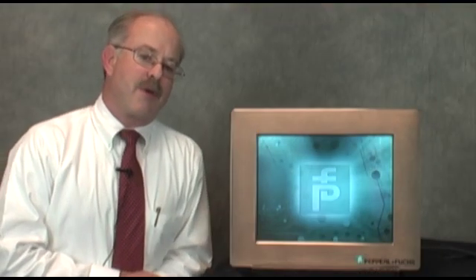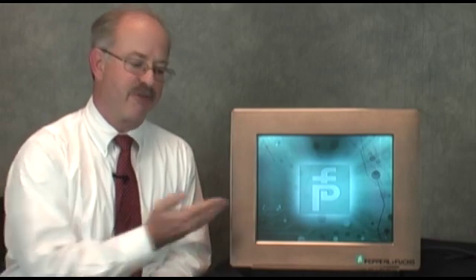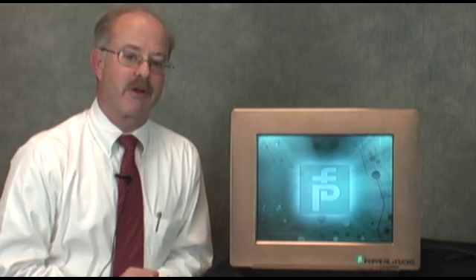In addition to the better operating temperature parameters, a true industrial grade LCD panel is typically much brighter than a consumer grade LCD panel, 40 and 50 percent brighter in fact. Our 15 inch design features 500 nit lumen output as standard, very appropriate for a well-lit industrial area.